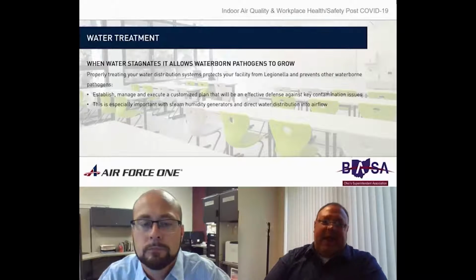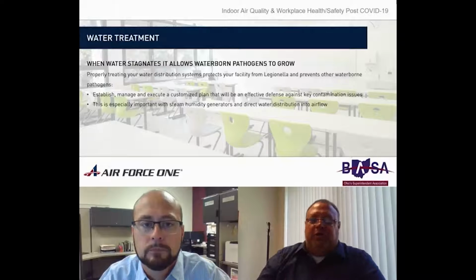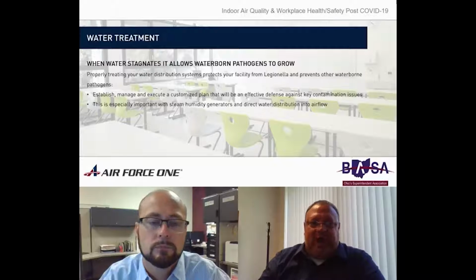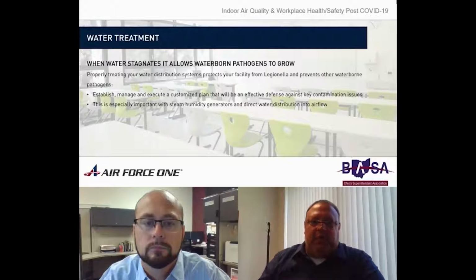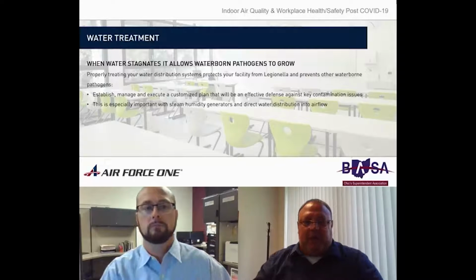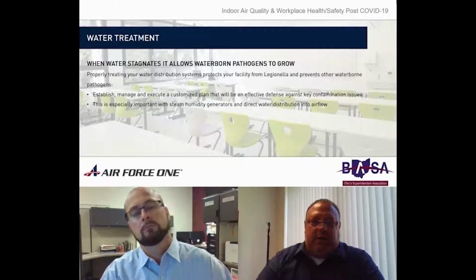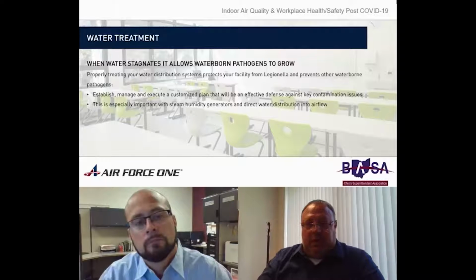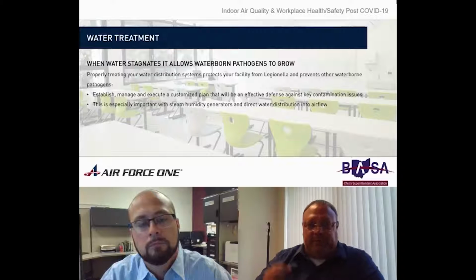Right. Well, from a mechanical standpoint, one of the things you have to look at when you have, say, a cooling tower is it is a huge air scrubber. So as the water is falling through the tower and evaporating and cooling off, all the air that's pulled through there, and of course all the dust, mold, mildew, gets trapped in the water, goes into the water, and then builds up inside of your sumps, and also builds up inside of your pumps and all of your pipes inside.